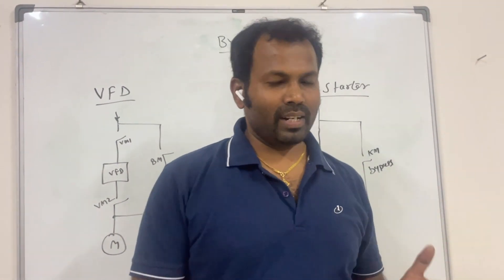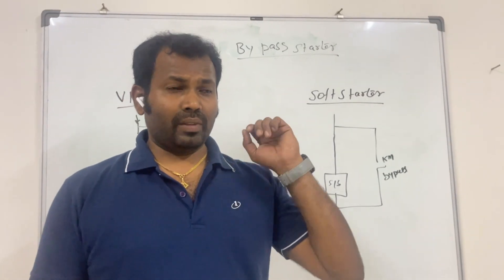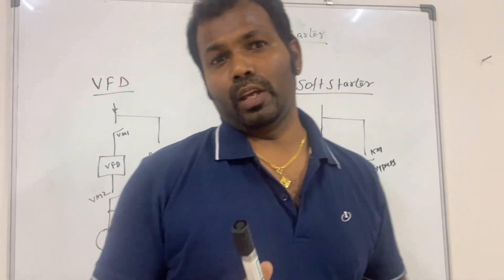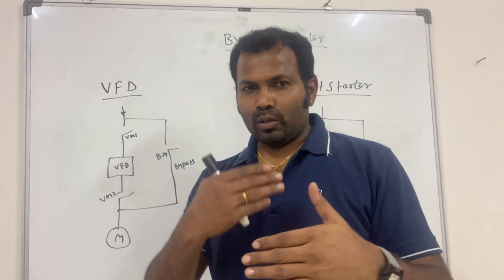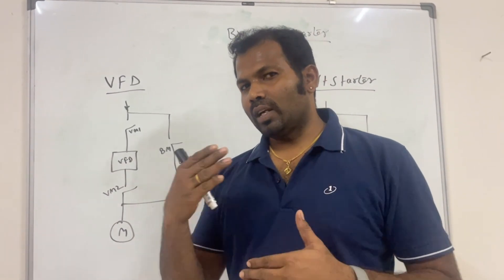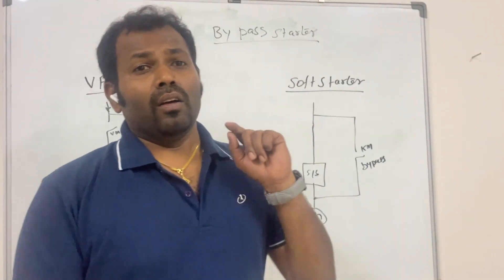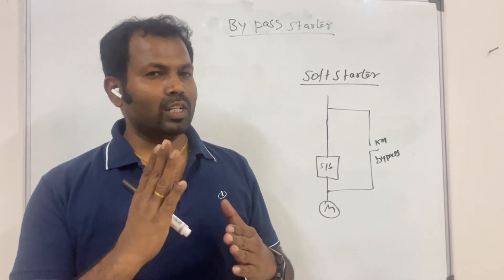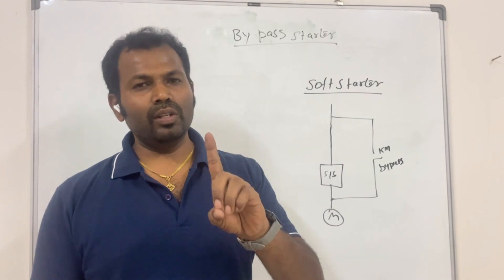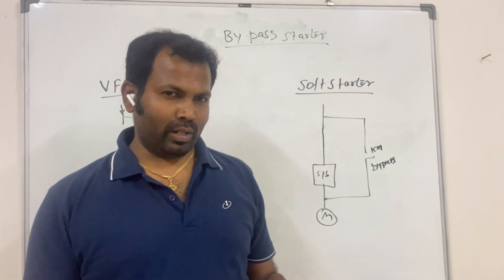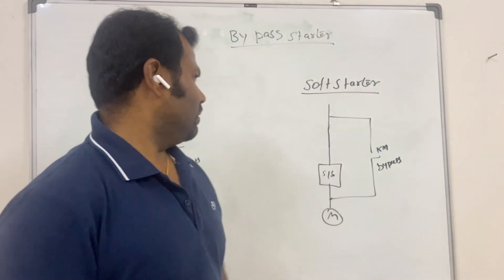We will see the difference between VFD bypass starters and soft starter bypass starters. VFDs are normally used to control the speed of equipment or motor, and also to give a smooth start. Soft starters are used only to give a smooth start — we cannot control the speed with a soft starter. So the key difference: VFD gives smooth start and speed control, soft starter gives smooth start only.